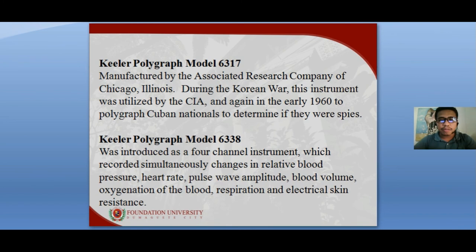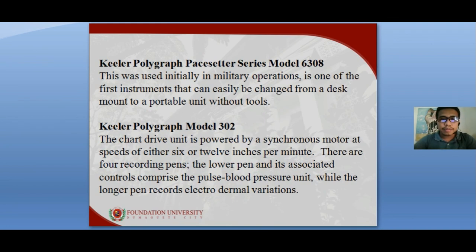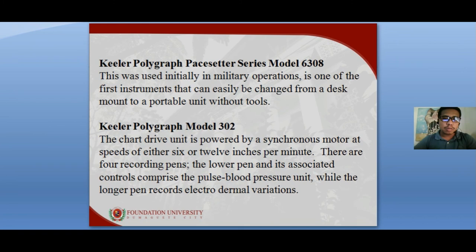Another model is the Keeler Polygraph 6338, introduced as a four-channel instrument that simultaneously recorded changes in blood pressure, heart rate, pulse wave amplitude, blood volume, oxygenation of the blood, respiration, and electrical skin resistance. Model 6308 was used initially in military operations and was one of the first instruments that could easily be changed from a desk mount to a portable unit without tools. Model 302 features a chart drive unit powered by a synchronous motor at speeds of either 6 or 12 inches per minute, with four recording pens.